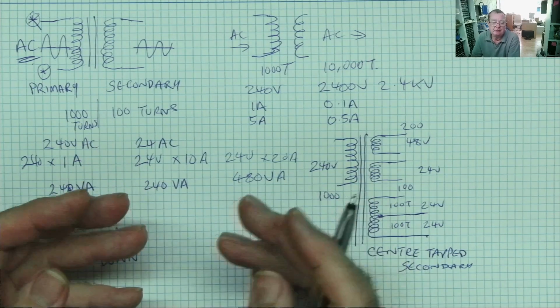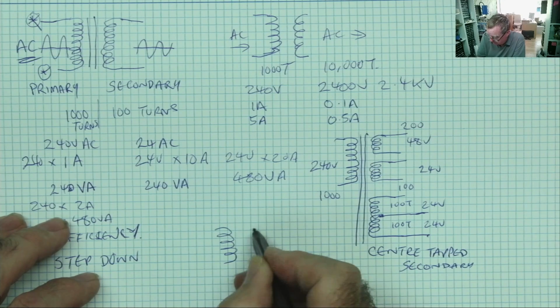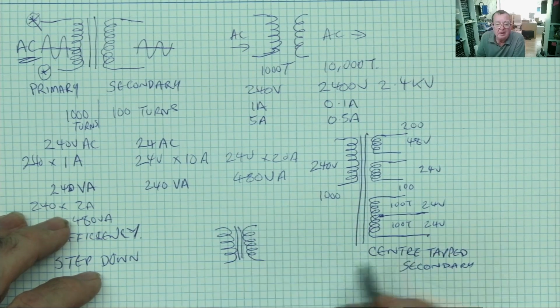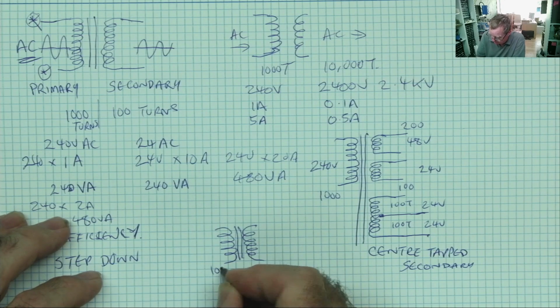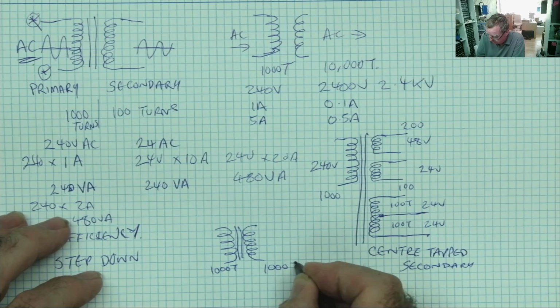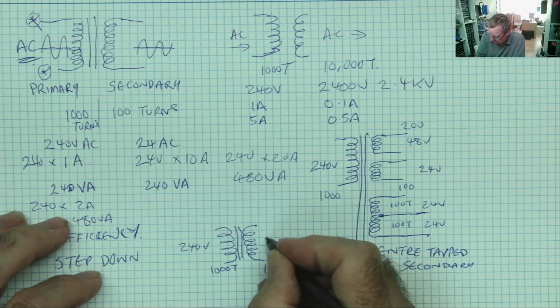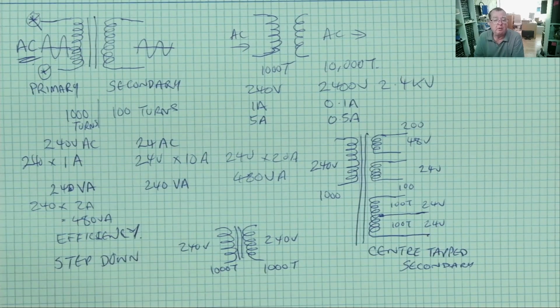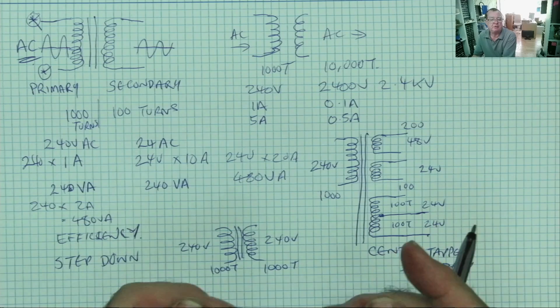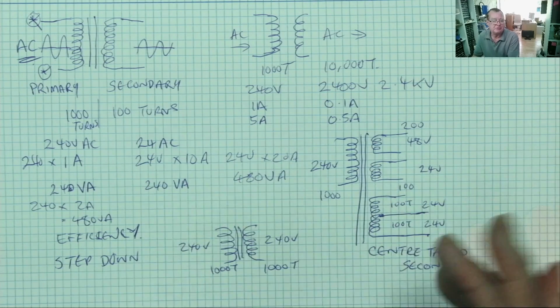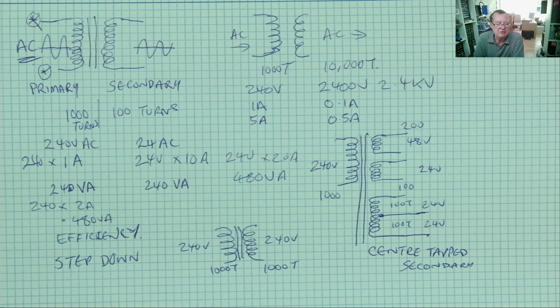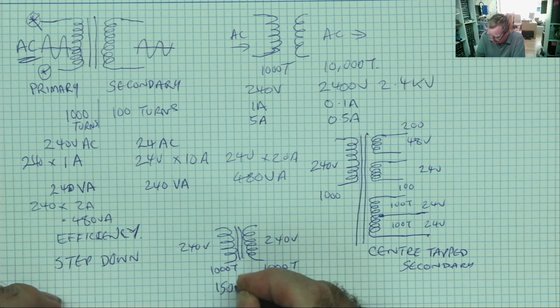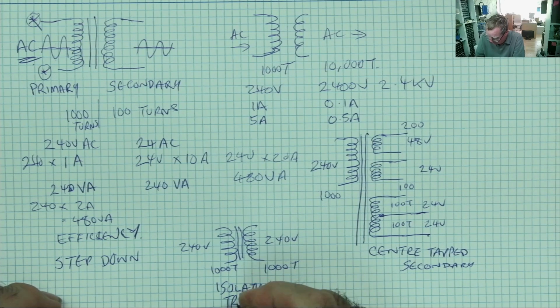You can also get transformers like this. 1000 turns, 1000 turns, okay? 240 volts, 240 volts. What use is that? Because whatever voltage we put in at whatever current, we get the same voltage at the same current coming out, less the efficiency loss, which causes the transformer to warm up. So this looks like it's doing nothing useful other than wasting a bit of power. But what this is doing is actually something very useful. So this is called an isolation transformer.